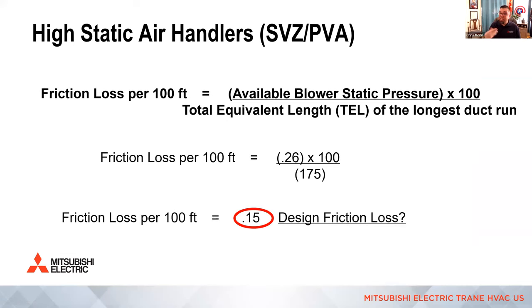So we're going to actually plug these two numbers in to see what the friction loss is for this higher static air handler or mid static air handler. You can see 0.26 is what was available times the constant of 100 divided by 175 feet, the equivalent length of the longest run. And we're right at the maximum when it comes to design friction loss. Remember, the maximum you can design around is 0.16. What this is telling me is we need to slow the fan speed down or use a couple of bad fittings to get the friction loss lower. Otherwise, we're gonna have a noisy system, all right?